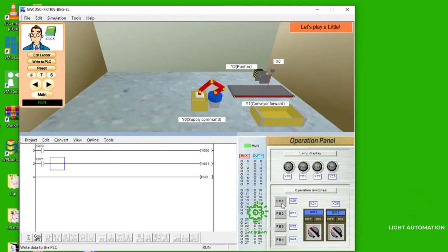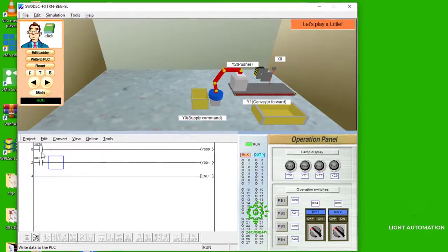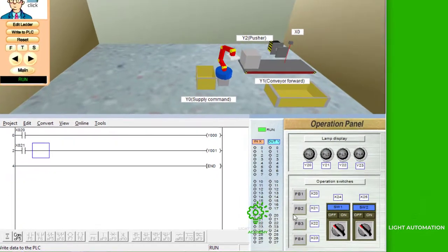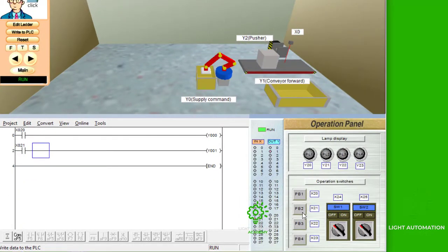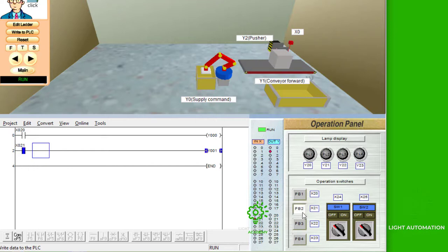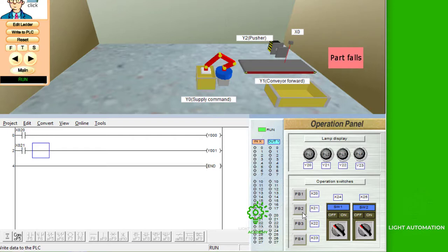When I supply product to the conveyor using x20, which is addressed to this input, when I press x21, my conveyor stopped. Immediately I remove my hand from it, I have to press it down for it to continue running. Why? Because it's a push button. A push button is a spring-loaded button. It requires you to continually press it down for it to allow current to pass.